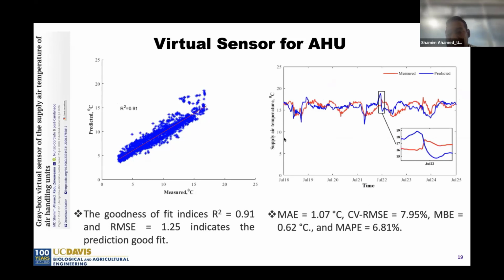The next part is, our goal was to predict the supply air temperature. For doing that, we need to also do the temperature modeling for the mixing box shown in the previous slide, where the return air is coming and mixing with the incoming air. That graph shows how this gray box model can predict the supply air temperature compared to the measured data, along with statistical parameters showing how accurately this model could predict it.